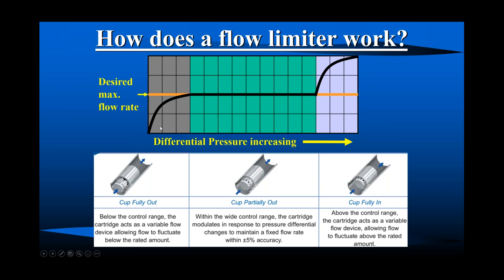So in this gray area, we have this flow here, and it's below the desired flow rate, so the automatic flow balancing valve isn't doing anything. It's fully out. It is a fixed orifice, if you will. It's sitting out there in the water stream. It only comes into play when you try to overpump it, trying to put more flow through the flow limiter than it was designed for. And then it starts to do its modulation, moving in and out of the can, providing a variable orifice.